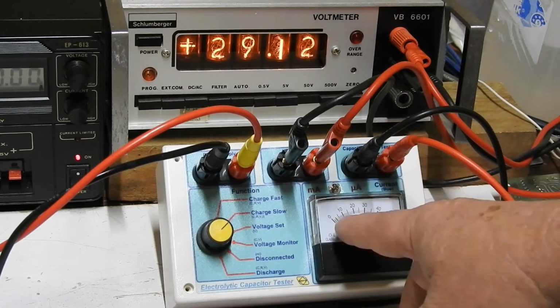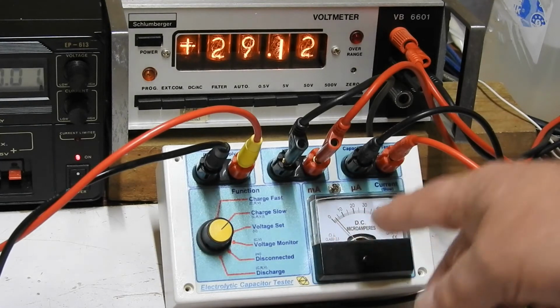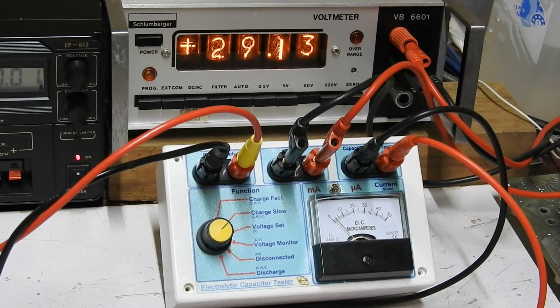So we have to go to milliamps, and there's about 1 milliamp of leakage, which is, I think, probably still within specs, although the formulas that the different manufacturers give make it a bit confusing, and it depends on whether you're talking about acceptance leakage current, which is after you've just let it run for 5 minutes, or operating leakage current, which is when it's had an hour or so to reform.